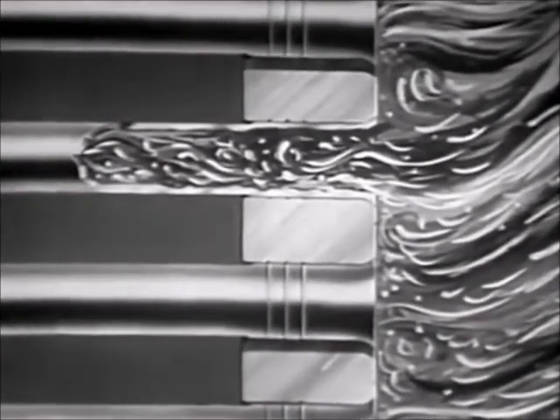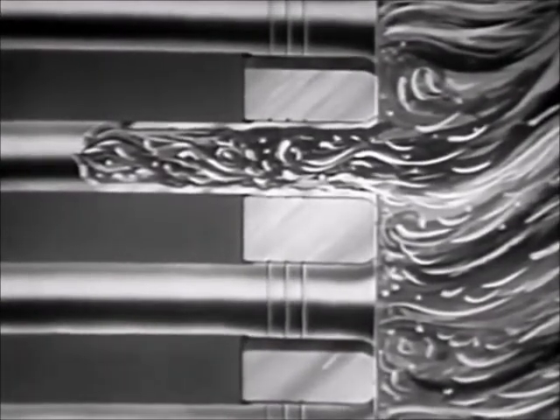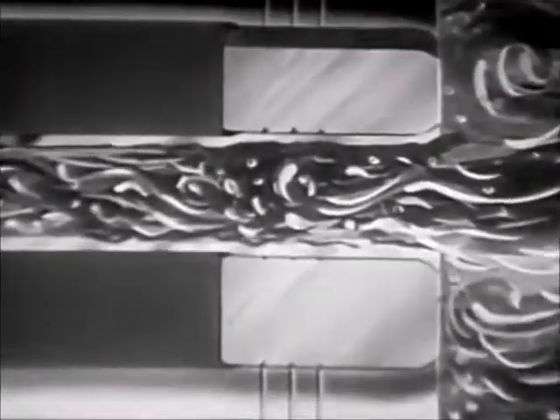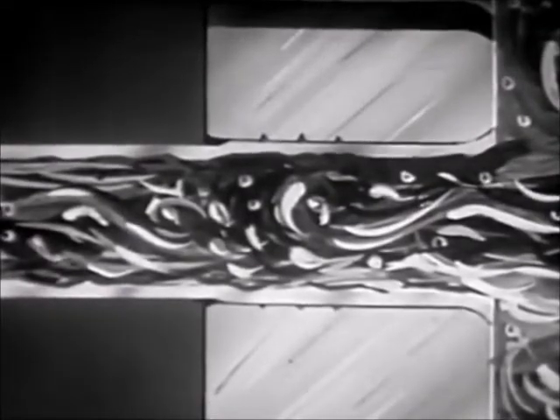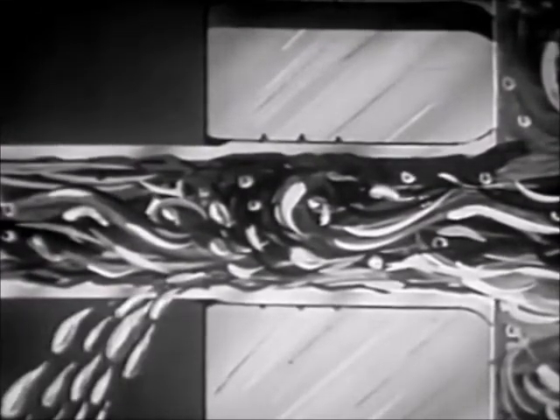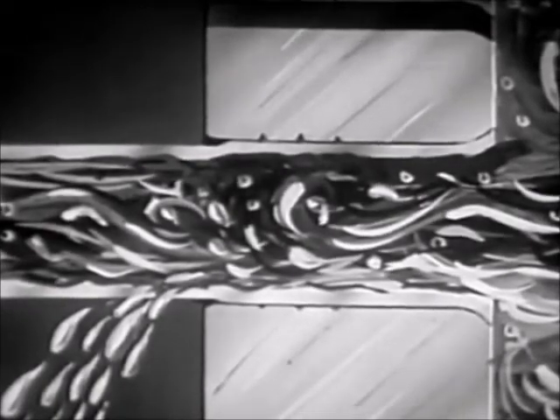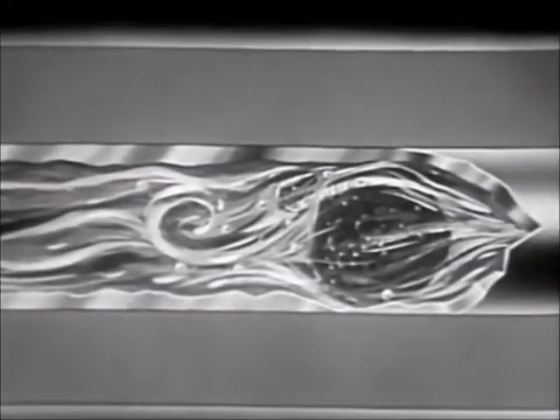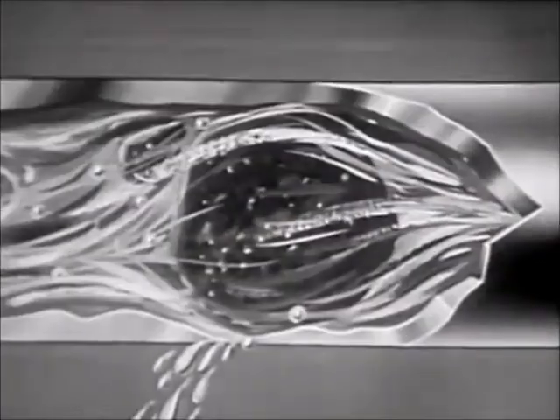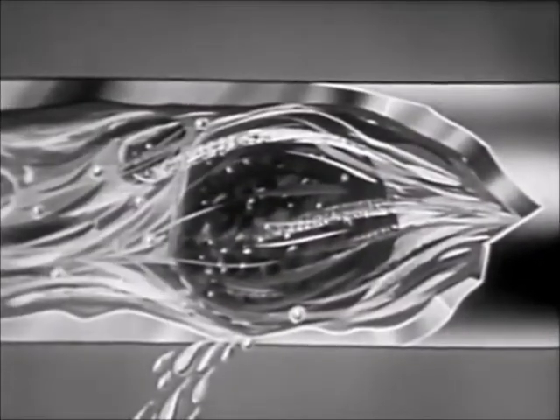Water turbulence in the inlet ends is another possible cause of tube leaks. Metal is worn away in what is called end erosion. If such conditions persist, tubes will fail near the inlet ends. Obstructions, too, can cause turbulence and erosion. In addition, there is pitting and often failure at the point of obstruction.